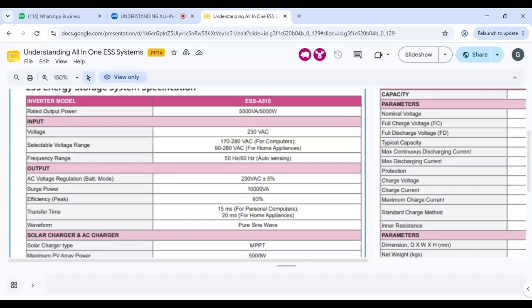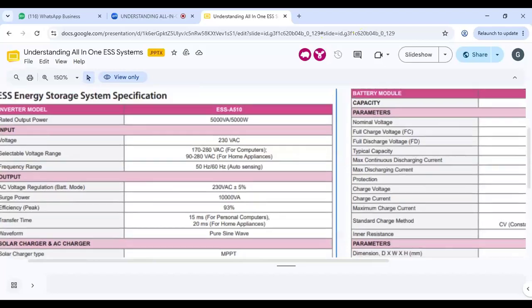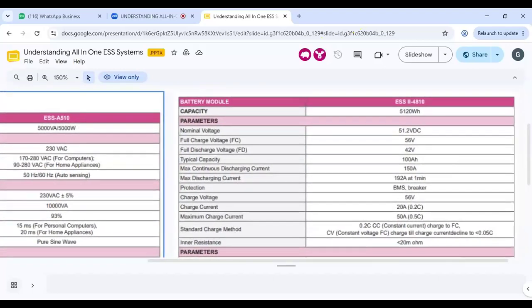Now let's go to the nominal voltage, which is for the battery now, which is 51.2 volts. You can see the low battery disconnect points. All these will be managed by the inverter itself.